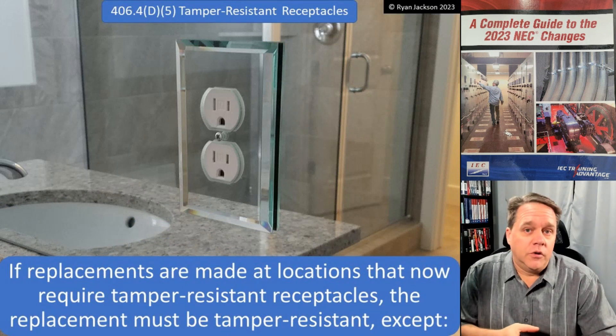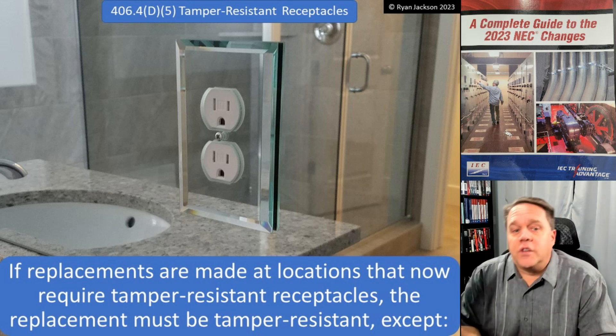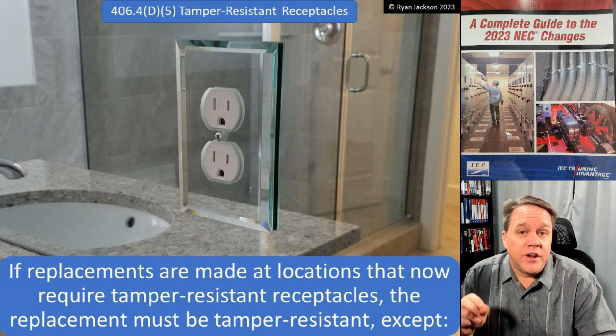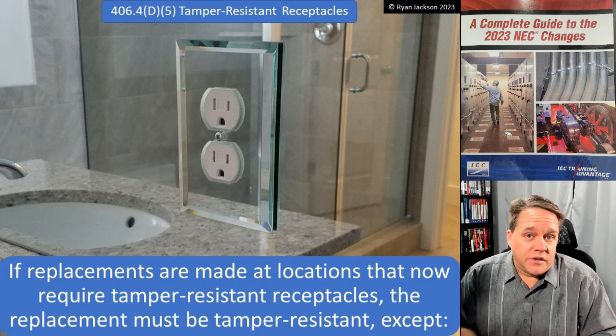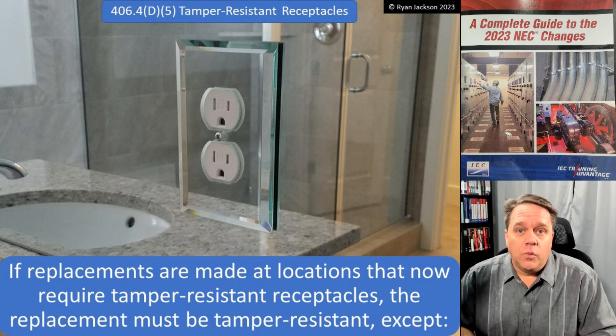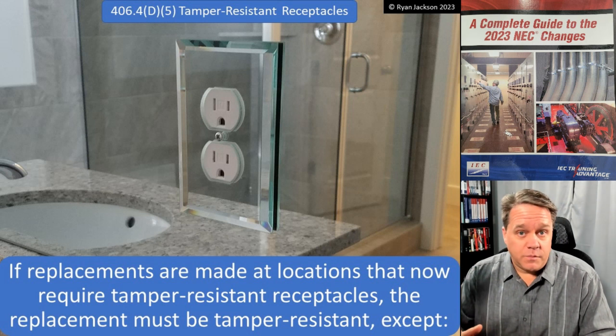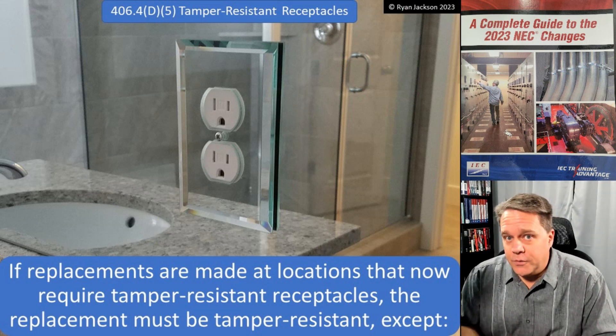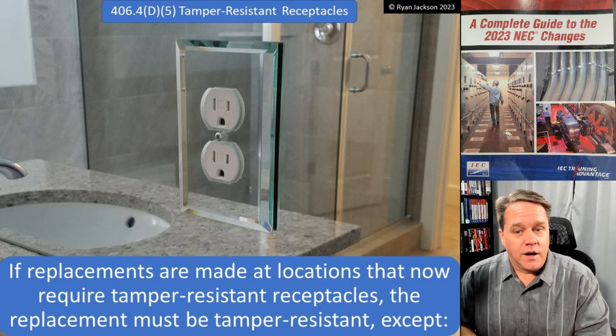I'm not going to read all of the replacement receptacle requirements, just the ones that changed. 406.4D4 talks about GFCI replacements. 406.4D5 talks about tamper-resistant receptacles — it says if replacements are made at locations that now require tamper-resistant receptacles, the replacement must be tamper resistant, with an exception. Where do you need tamper-resistant receptacles? You go to 406.12. Item one, which has been in the code since 2008, is dwelling units. If you're putting a receptacle in a house, it's got to be tamper resistant. So if you replace a receptacle in a house, it has to be tamper resistant — assuming 125 or 250 volt, 15 or 20 amp receptacles.